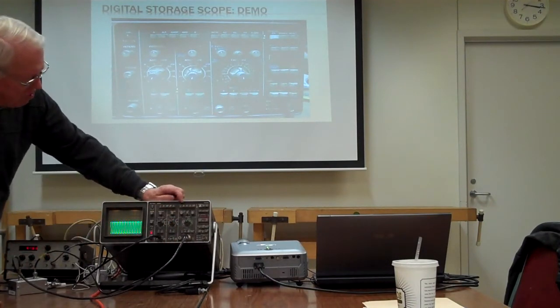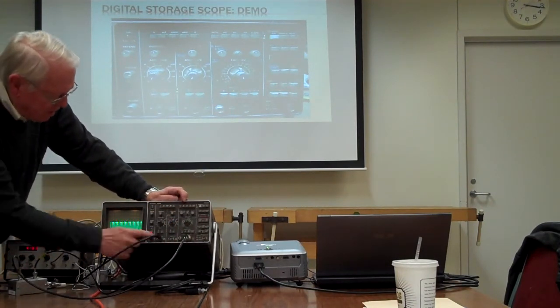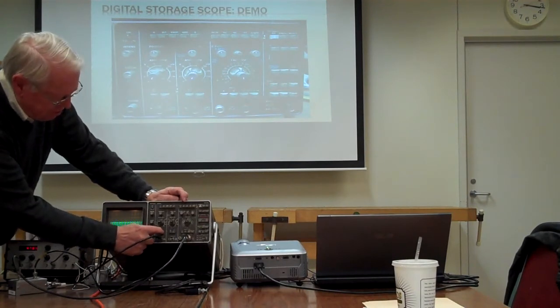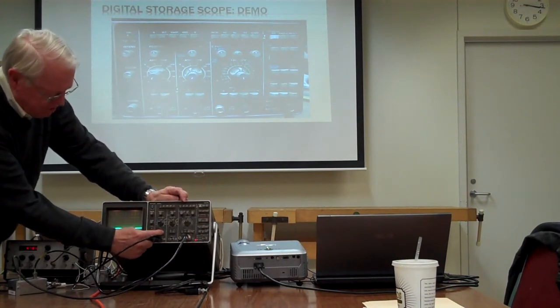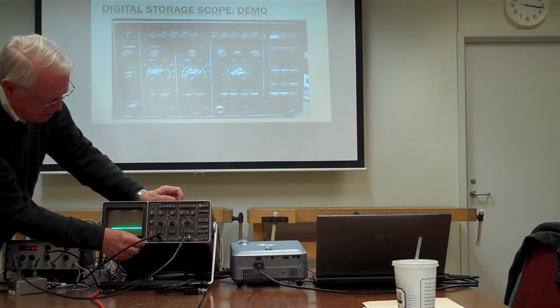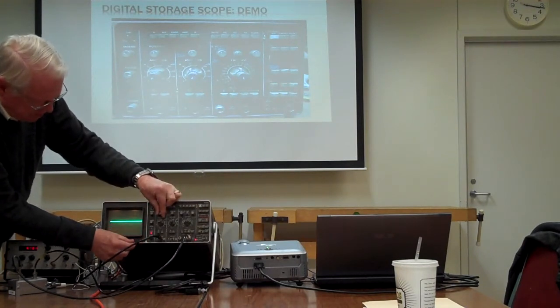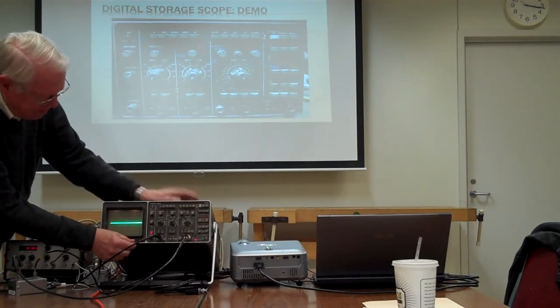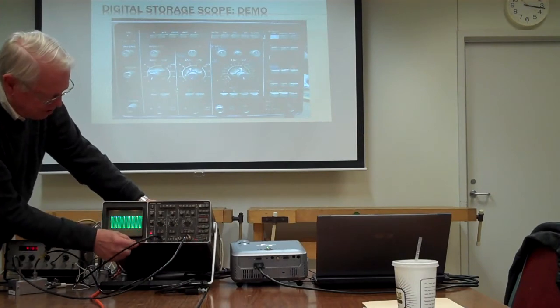And we've got it in auto mode right now. If I push the zero coupling down here, this gives me a straight line, then I can use the position reference to reference that at any point on the screen. I'll set it at center and release the zero.